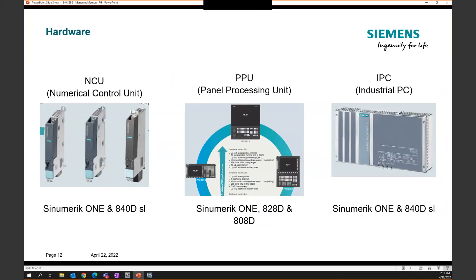For more elaborate systems, you can also have an Industrial PC — our IPC. The industrial PC still talks to the NCU; you'd actually have both pieces of hardware. The IPC is used when an OEM needs a Windows front end. Traditionally, the PPUs and NCUs run on a Linux operating system, whereas an IPC has a Windows environment but still communicates with the NCU. There's a lot more storage potential on an IPC because of its hard drives, compared to the CF card used to hold software and memory on an NCU or PPU.